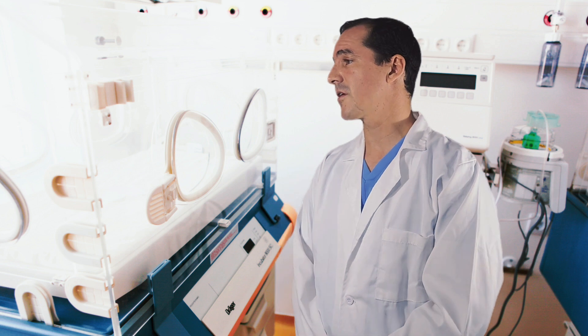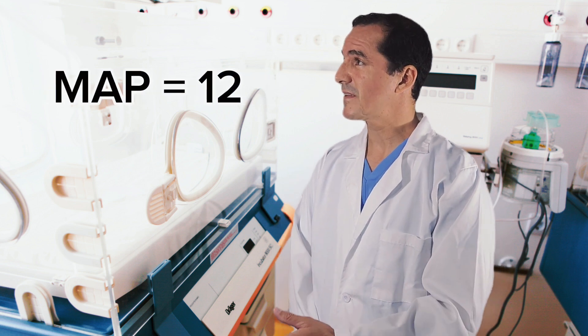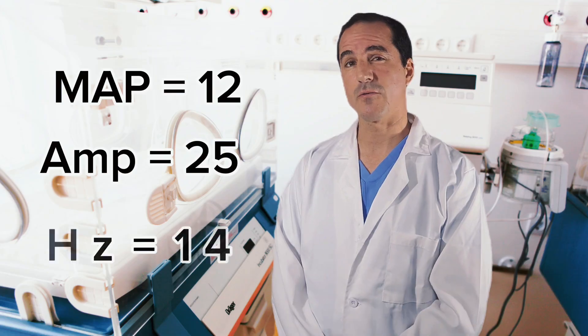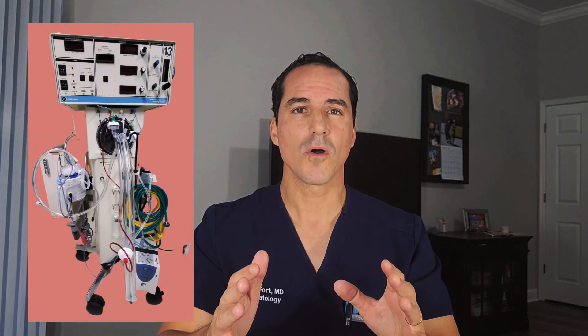Good question. Given the current settings that we have on mechanical ventilation, we should probably start at a MAP of 12. Let's give it an amplitude of 25 and hertz of 14. So why did Dr. Ford choose those settings? We're going to be talking about that a little bit later, but why don't I explain the oscillator to you?